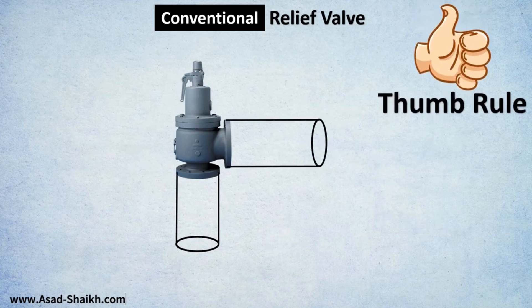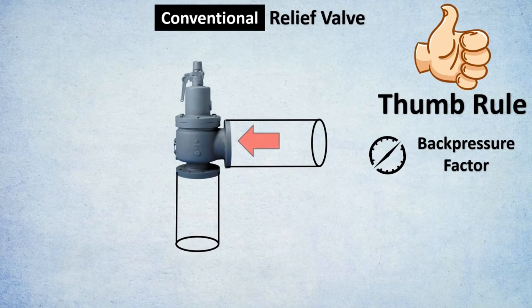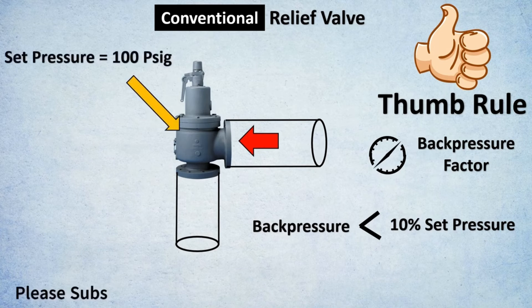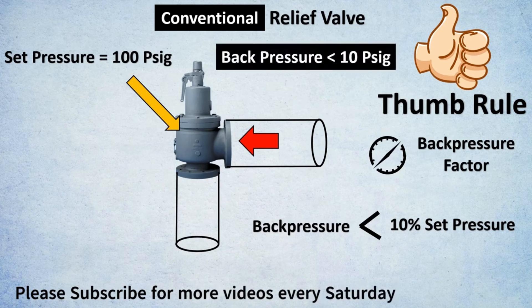The most important thumb rule when selecting relief valves is the back pressure factor. Back pressure is the pressure acting downstream of the relief valve outlet in the piping. For a conventional relief valve, the back pressure must be less than 10 percent of the set pressure. For example, if the set pressure is 100 psig, the back pressure should be less than 10 psig.